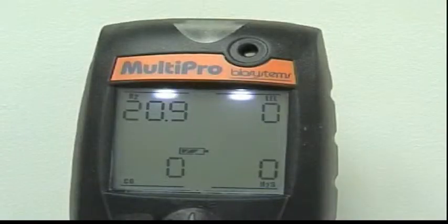The simplest way to test sensor response is by performing a bump test. Turn the MultiPro on and allow the readings to stabilize. 5 minutes is usually sufficient unless a sensor has just been replaced. See the MultiPro reference manual for further details on replacing sensors. Check the readings for fresh air.